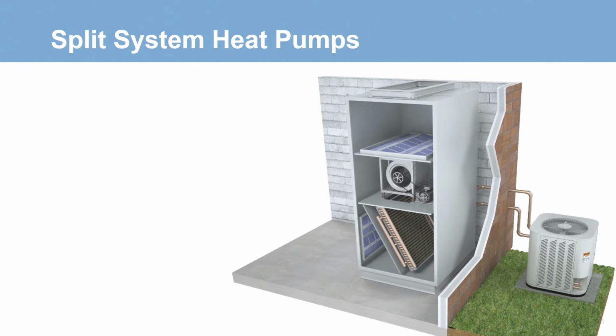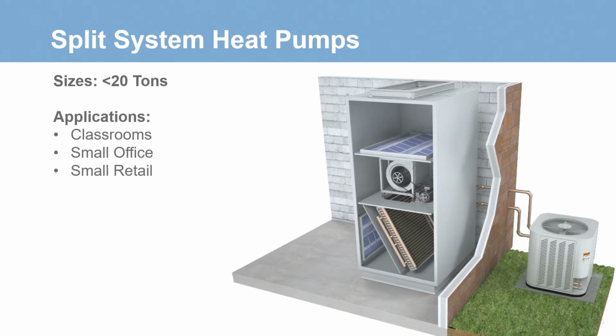These end up looking a lot like most ducted residential systems. Cooling-only versions of split systems can range in sizes larger than 100 tons. However, heat pump split systems are typically 20 tons or less. Applications best suited for split system heat pumps would be the light commercial space, small retail, small office, and classrooms.